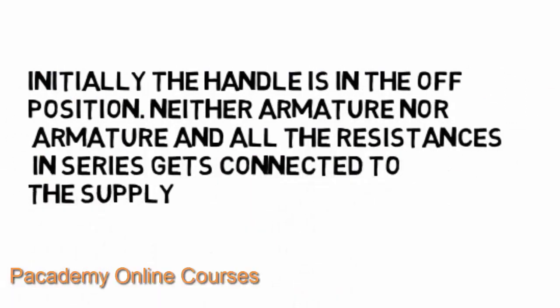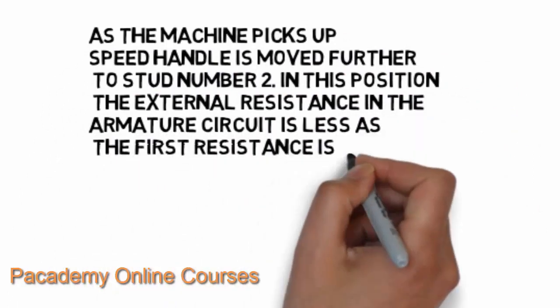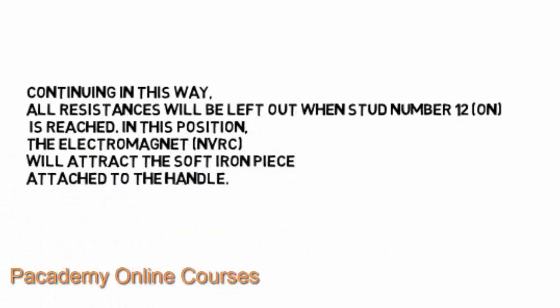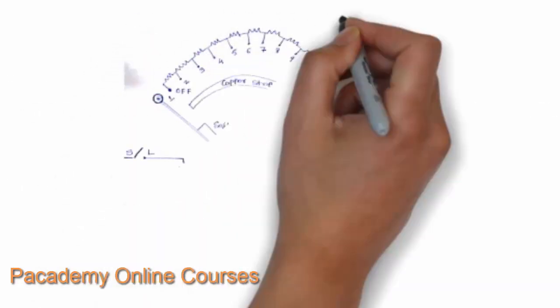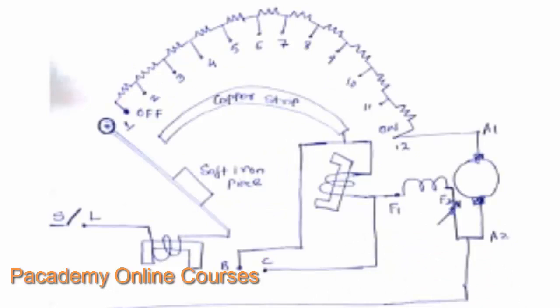Looking at the diagram of a three-point starter: initially the handle is in the off position, so neither the armature nor the resistance is connected to the supply. As the machine picks up speed, the handle is moved to position two, where the external resistance in the armature circuit is reduced. In this way, all the resistance is progressively cut off as the machine's speed increases. The electromagnet attracts the soft iron piece attached to the handle, keeping it in the final position with the field winding connected.